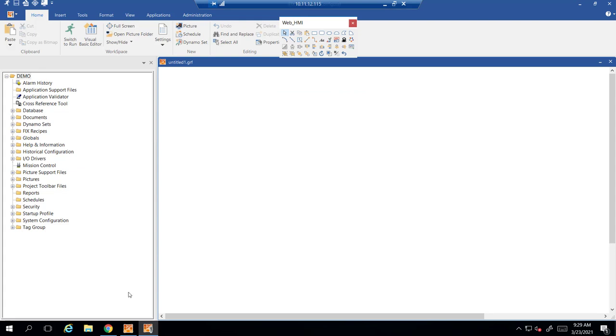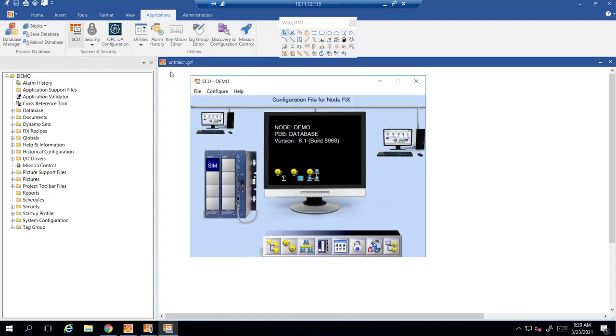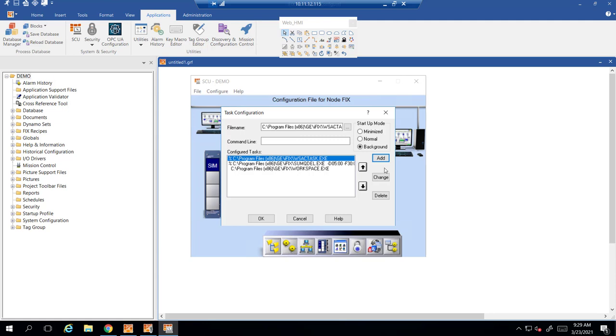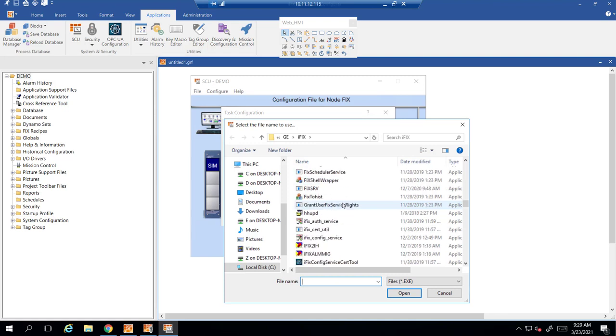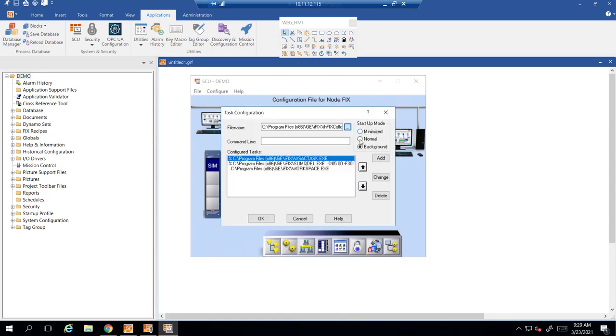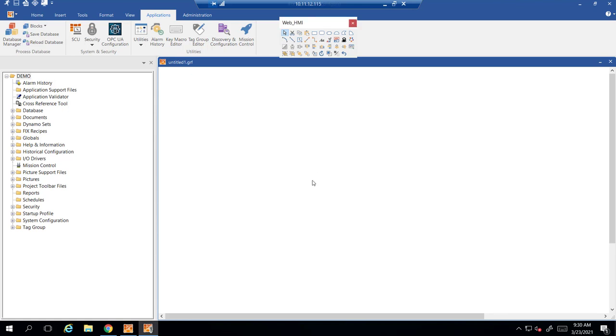This is the workspace. It is a task that is already pre-configured inside your SCU under the Tasks tab — this is where you do most of your configuration and pictures. From the SCU, go to Tasks. As a quick example, if you wanted to add one, go to the ellipsis on the right, find the EXE you'd like to run — for instance, the Historian Collector. Go down and look for the iFIX Collector, hit Open, hit Add, hit OK. File Save — always save — and you're good to go.